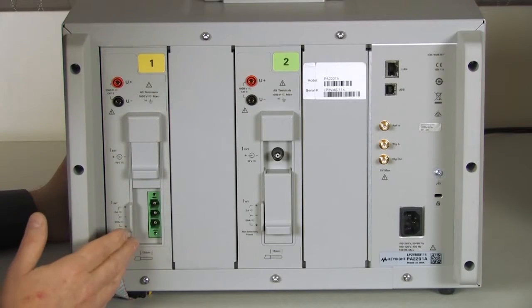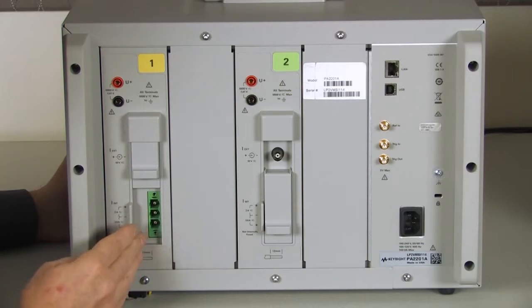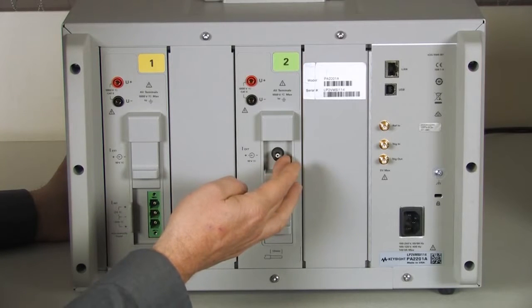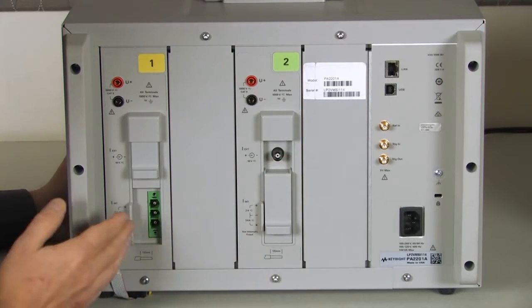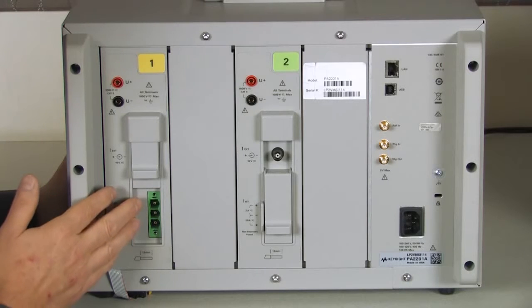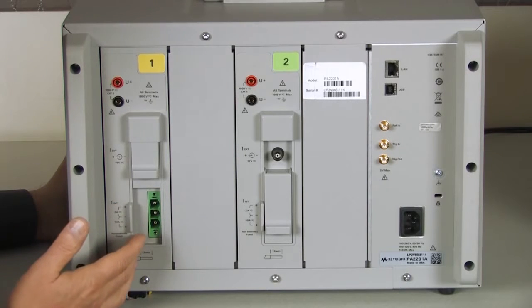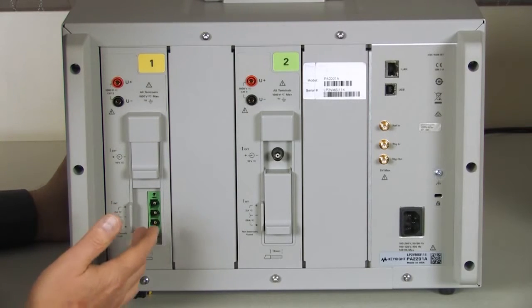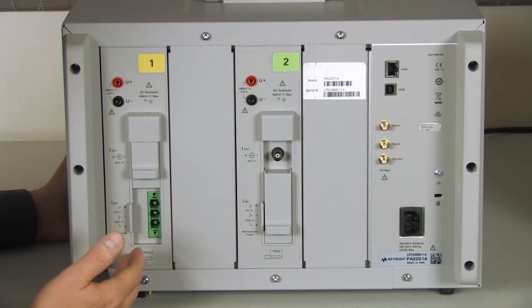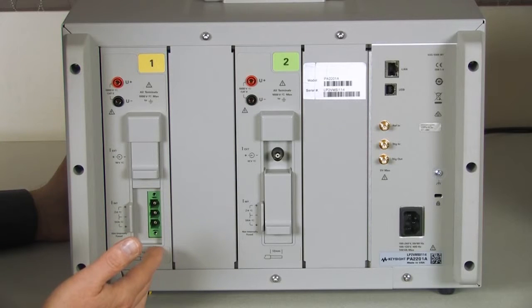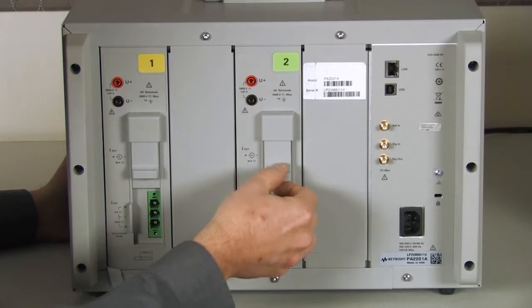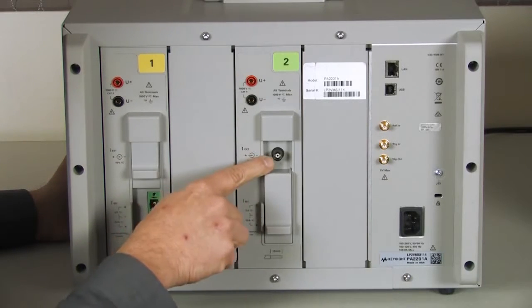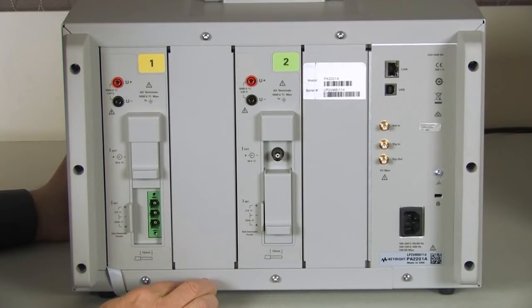The current connections come in two varieties: either our direct connection or a BNC connection for external probes. The direct connection has both a 2 amp and a 50 amp connection, which then go through a shunt built into the system. If you have currents higher than 50 amps, you'll move the slide down to expose the BNC connector for external probes.